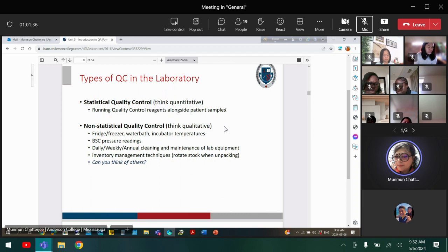A known amount of material, where you know that if you run this one, it is going to give 2 millimole per liter. I know that one. The machine analyzer has to give that value. Then the machine is working properly. When I have a known dilution of RBC or WBC or anything, they have standardized it and you run it, so you know this normal standard is giving the same value. It matches the same standard solution. That means the machine is working.